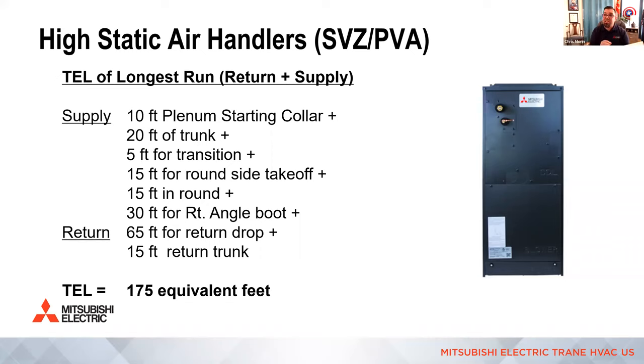If you keep a duct system simple using really low fitting values, you can actually run into trouble with friction loss on the high end, okay? Now, of course, on the return side, it's the 65 foot right angle return drop we talked about earlier that's typically used. And then 15 feet of return trunk that just went over to a floor register, central return in that first floor of a colonial or cape, all right? Not normal duct design, but you see it a lot on system replacements. That's why we're using this.